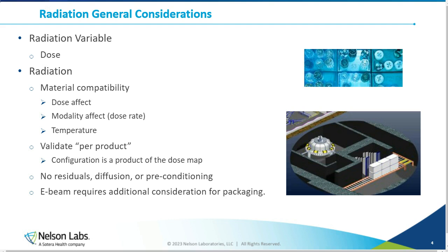And as such, we don't have to worry about off-gassing, and we also don't have to worry with radiation about preconditioning. One other consideration, and this is one of the reasons one of my associates is joining us today, is that E-beam needs some consideration because it is not able to handle density as well as gamma, for example. That doesn't mean it's not a better method or a comparable method. It just means that there needs to be additional consideration. So with E-beam, to account for that density, it's very important that you give additional consideration to your packaging. We want to present a very similar target for that product.